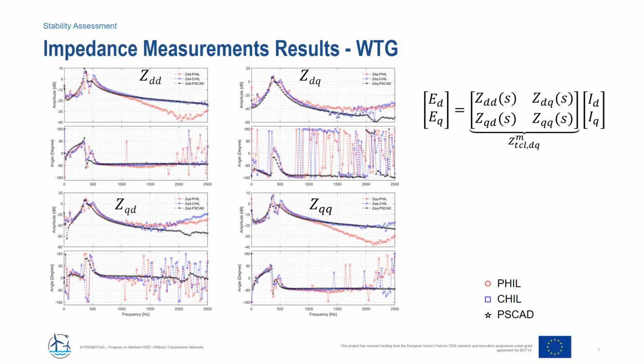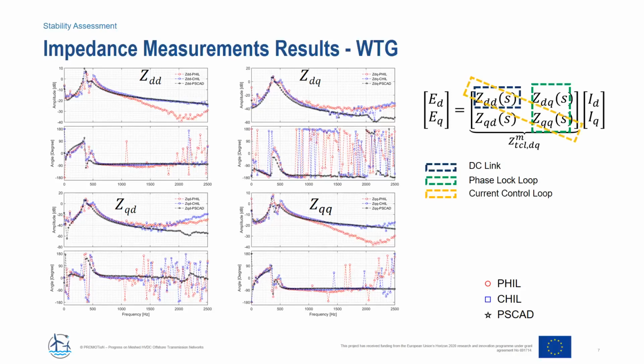And then in the 2x2 matrix, ZDD actually represents the characteristic of the DC link. The ZQQ is actually the phase lock loop characteristic, which very often shows up in the medium frequency range oscillation. The diagonal component is actually the current control loop representation.